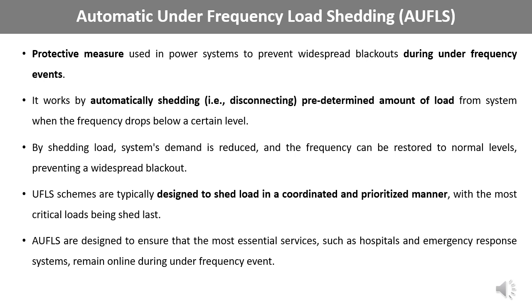Automatic under-frequency load shedding, or UFLS, is an essential protective measure used in power systems to prevent widespread blackouts during under-frequency events. Under-frequency events can occur due to several reasons including sudden loss of generation, increase in load demand, transmission line or equipment failures, frequency regulation problems, overloading of distribution networks, and failure to follow grid codes. UFLS works by automatically shedding a predetermined amount of load from the system when the frequency drops below a certain level. By shedding load, the system's demand is reduced and the frequency can be restored to normal levels, preventing a widespread blackout. UFLS schemes are typically designed to shed load in a coordinated and prioritized manner, with the most critical loads being shed last.